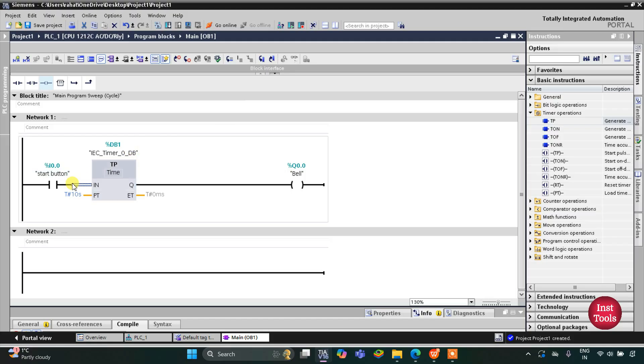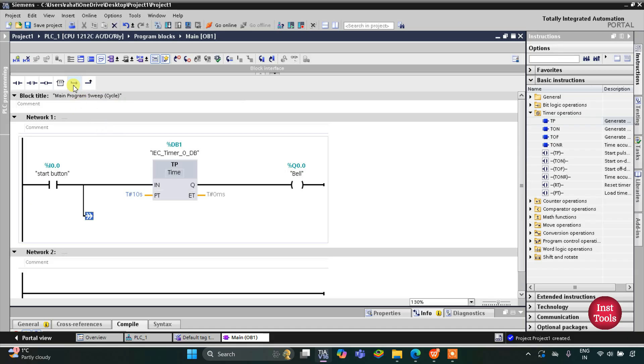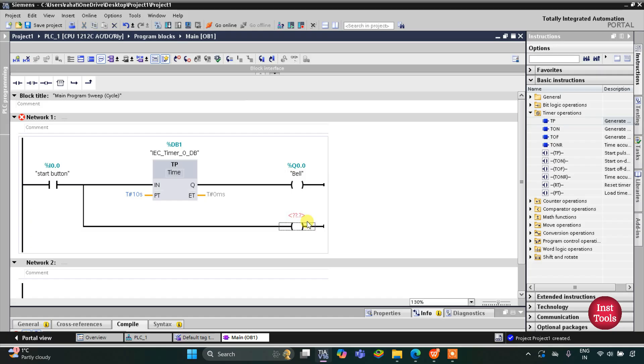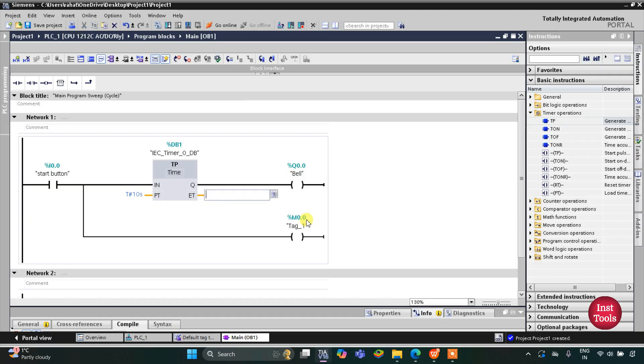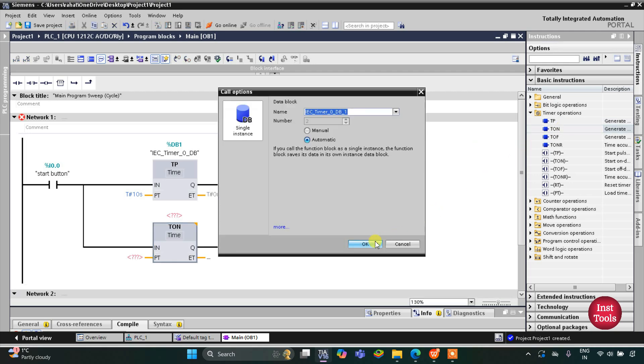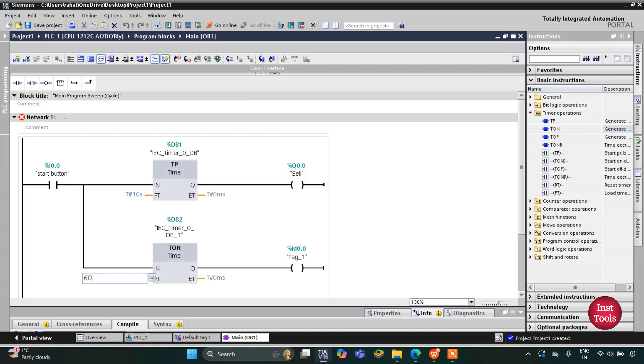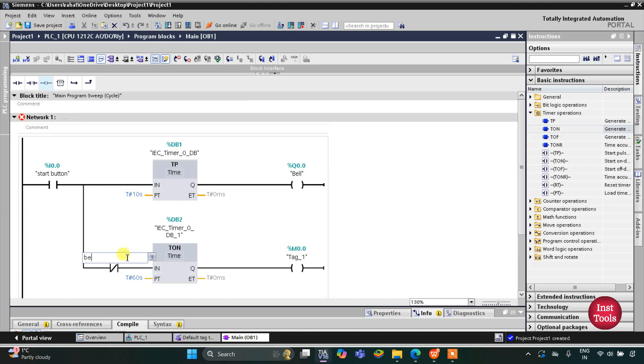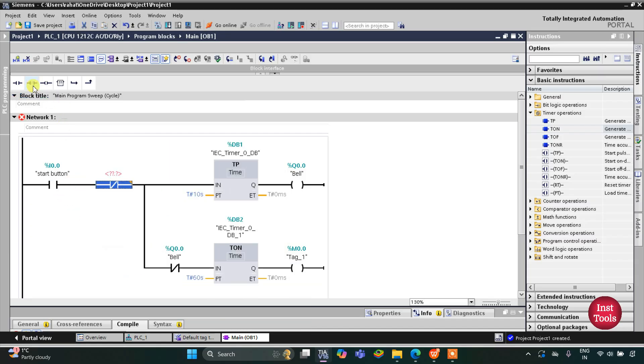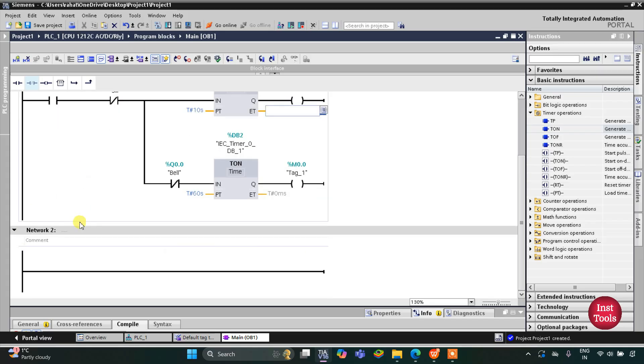After 10 seconds the bell will turn off, and it stays off for one minute. I will open a branch and add a coil for memory bit M0.0. This M0.0 should get on after one minute, so the preset value for TON will be 60 seconds. With that, I will insert a normally closed contact representing the bell, and another normally closed contact for M0.0.